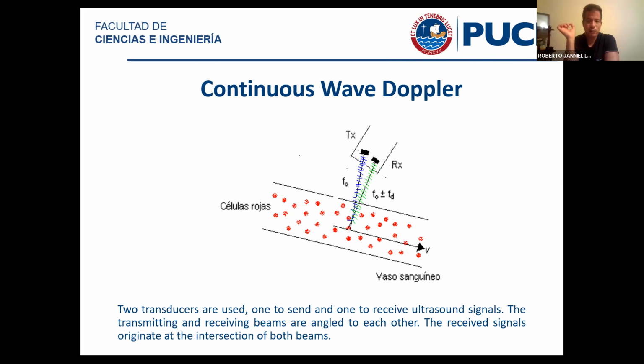The signal that comes back from the blood is really, really weak. So weak that if you analyze the amplitude only, it looks black. It looks like there's nothing in there. But it's not completely black. If it were completely black, then we wouldn't be able to produce Doppler images. The beauty of this is that the signal is weak, but it's there. So that's one of the reasons why Doppler imaging is very, very complicated to do.